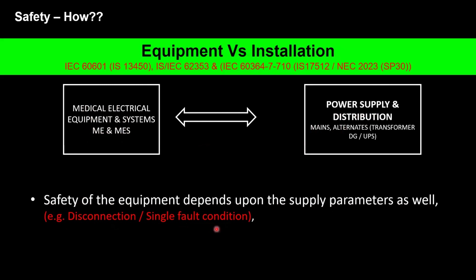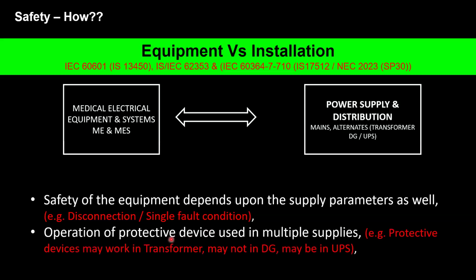What is the single fault condition? I will show you from the standard. Then the second part, operation of protective devices used in multiple supplies. Example, there is a DG, there is a transformer, there is a UPS. Please note, a protective device may work on the transformer. When the supply is from the transformer, the protective devices are ready to trip. That may work, but they may not work on the DG, and they may work on the UPS. So the situation is not sure whether the protective devices will work in all the conditions. I will just show you how these are transferred into the engineering practices.